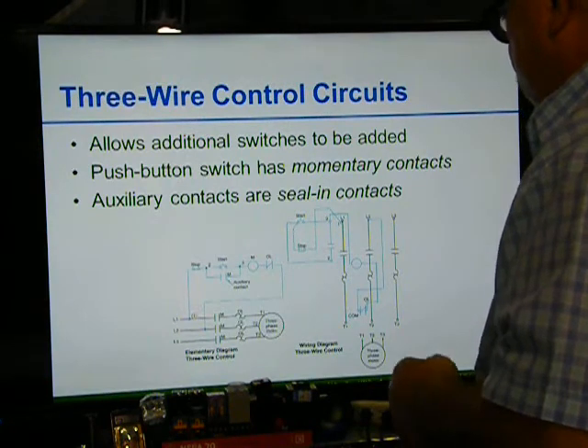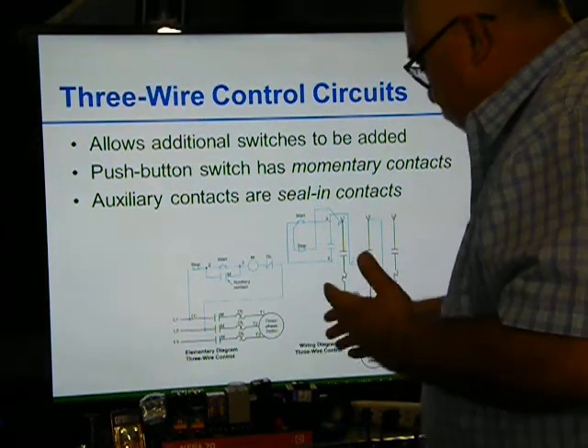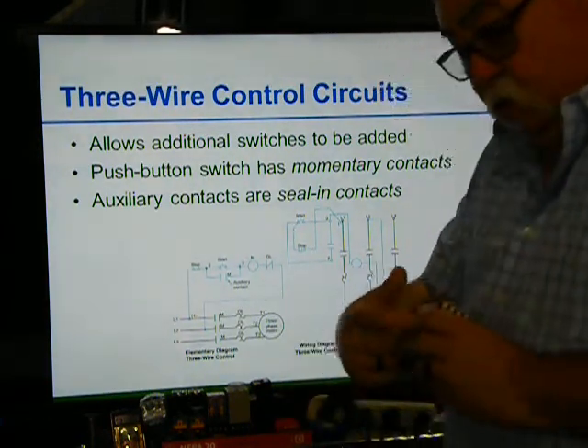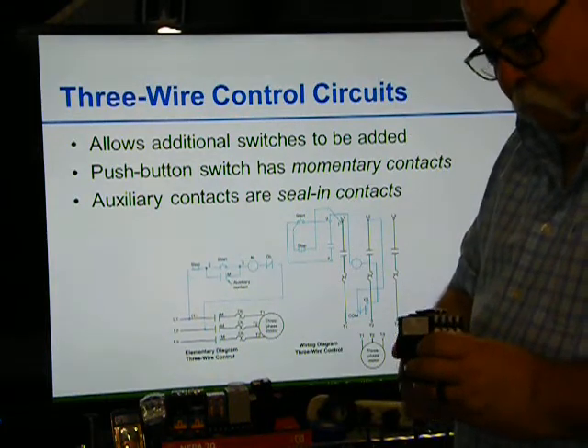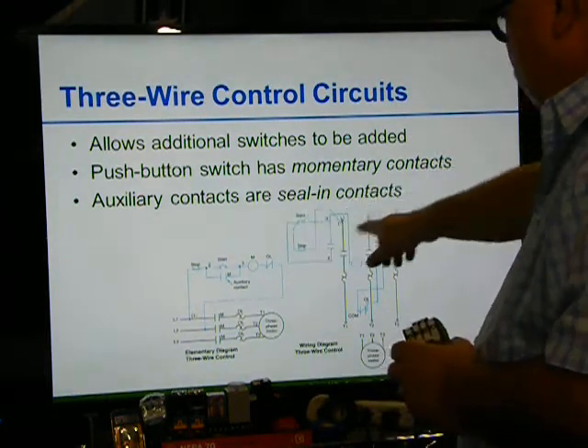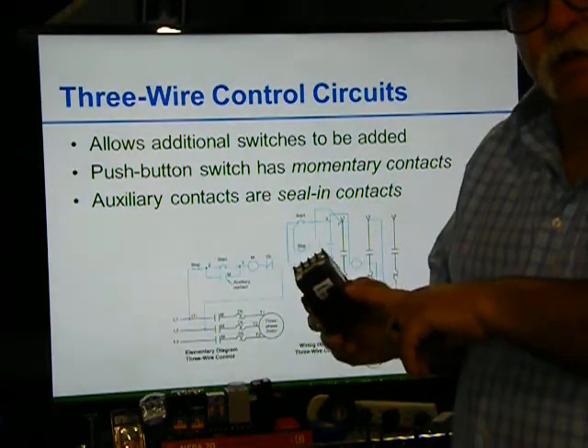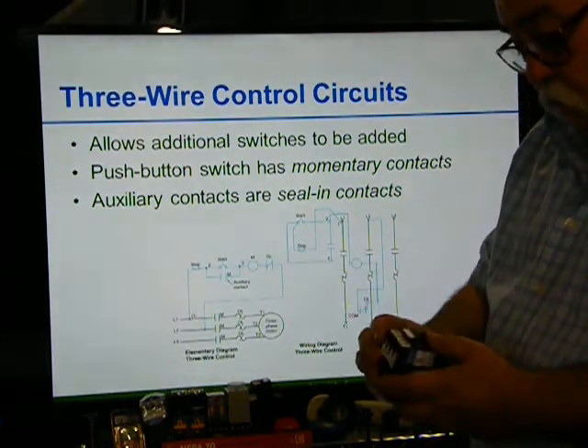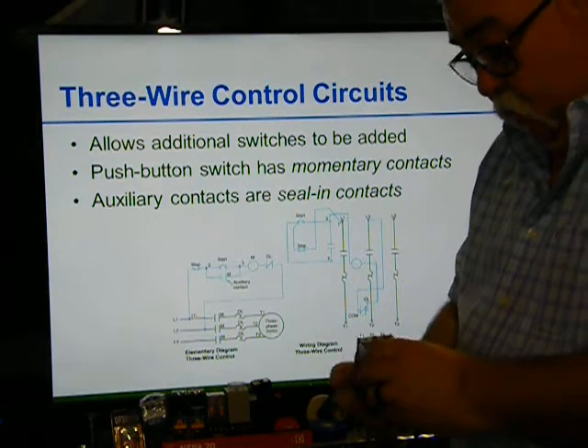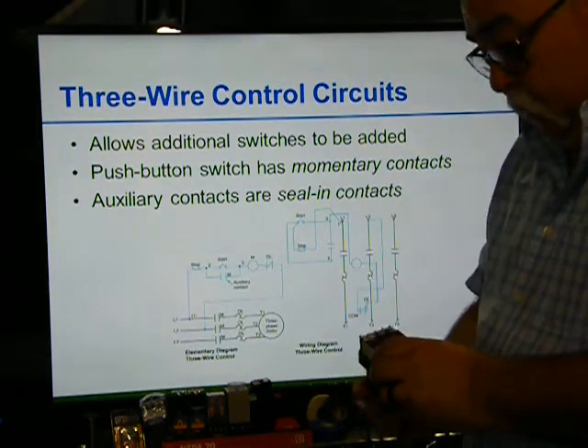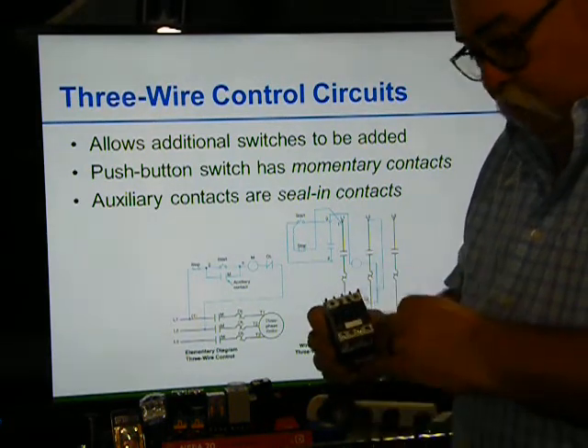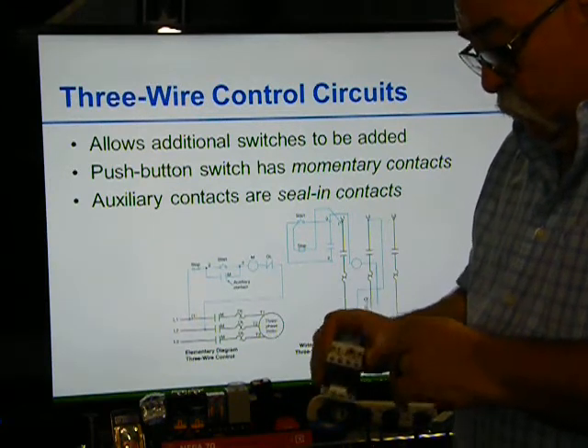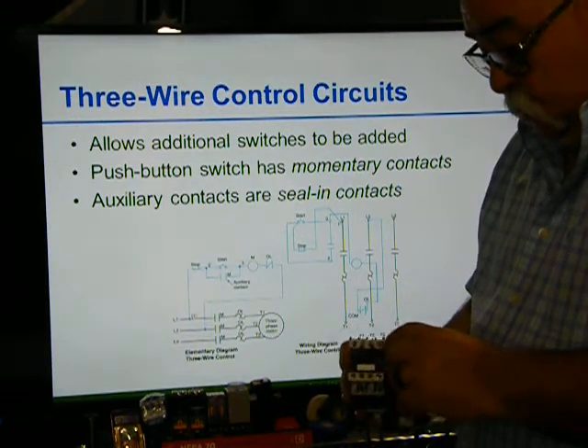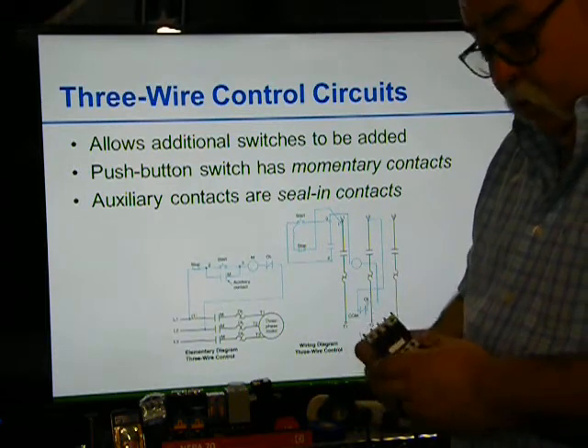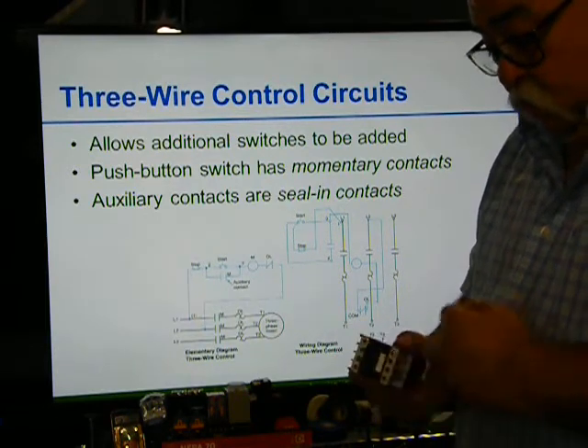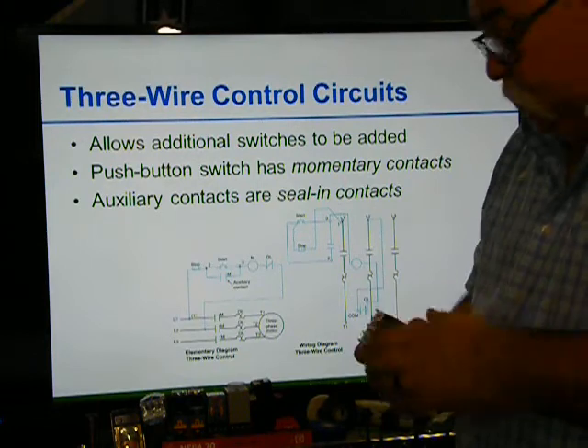Auxiliary contacts. So on your starter, it has an auxiliary contact. This one has an auxiliary contact internally. That's why they're called auxiliary contacts, or seal-in contacts. They're inside here. So when power comes across, like I was showing on the video that I sent out Friday, when I had these up close, you have the 3 and the 4, and then the A2. So the 3 and the 4 is your normally open, and that's where the contact's at. So once you hit that start button, it sends power across.